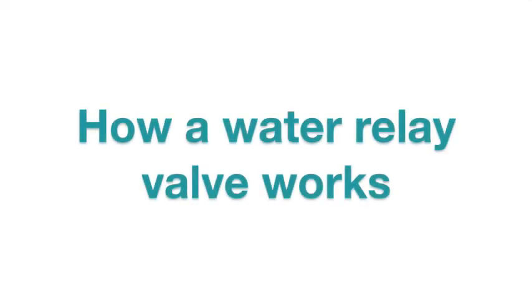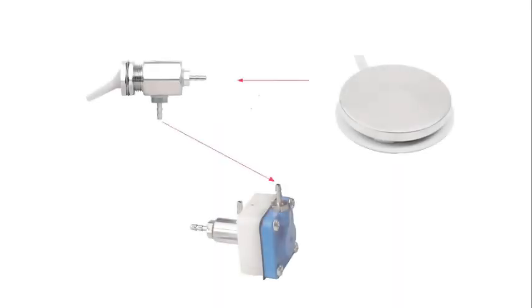A water relay valve works in conjunction with a relieving on-off toggle. When the unit's foot control is depressed, an air signal is sent to the relay valve to activate it, and the water will begin to flow to the hand pieces.